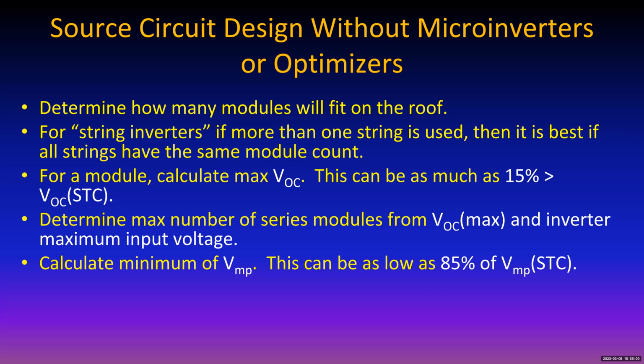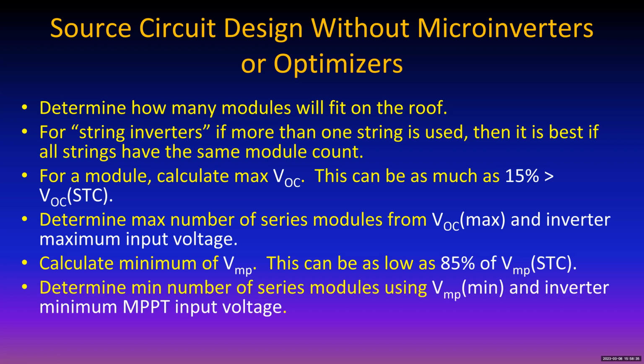And that's because if the maximum power voltage drops too low, then the maximum power point tracking inputs don't track maximum power anymore, and you don't get the maximum out of the system. So the minimum of the maximum power voltage could be as low as 85% of the standard test condition, depending on how hot it gets. The maximum of the open circuit voltage depends how cold it gets outside, and the minimum of the maximum power voltage is determined mostly by how hot it gets. And so then we can use the minimum maximum power voltage to get the minimum number of series modules, and of course it depends on the inverter's minimum MPPT voltage. I'm getting too many M's here. I'm getting a little tongue-tied.